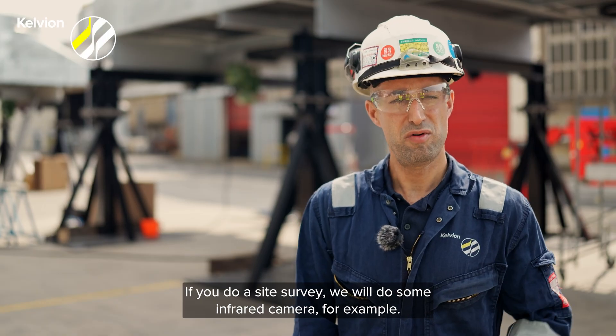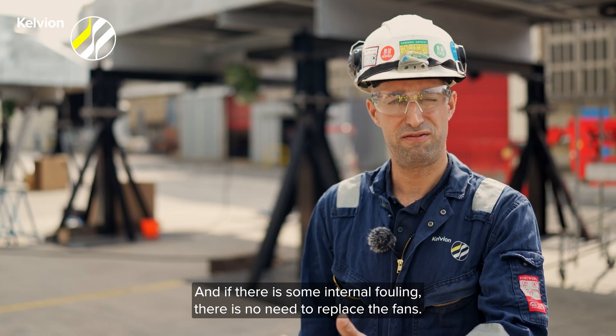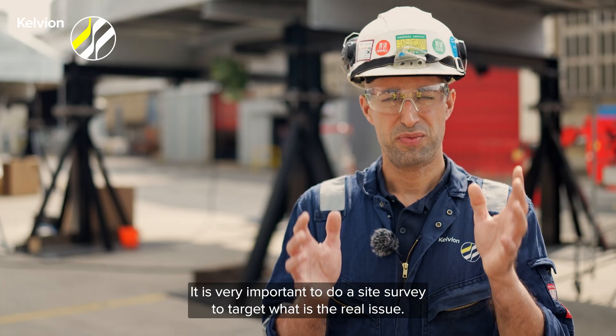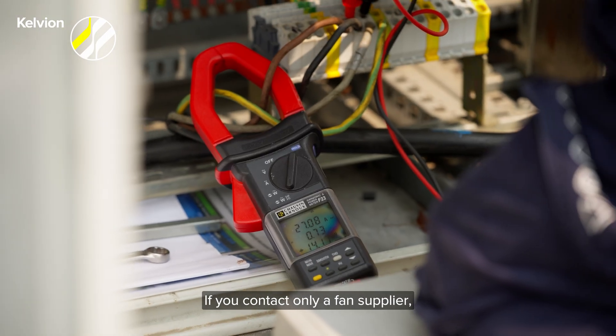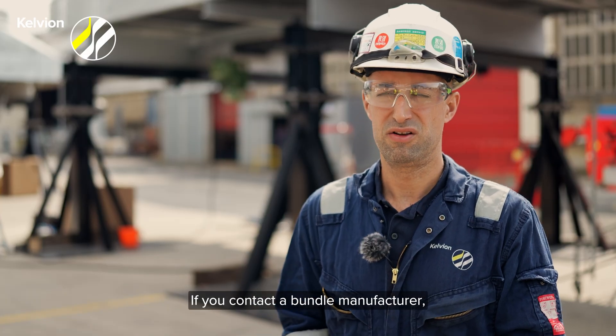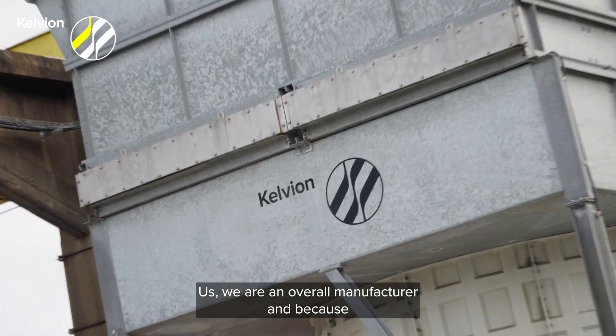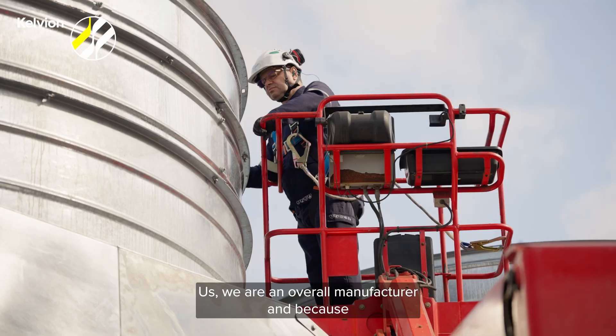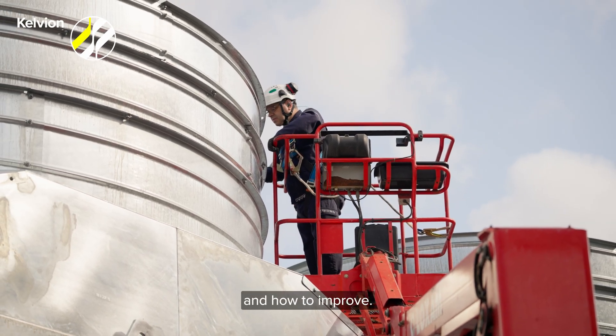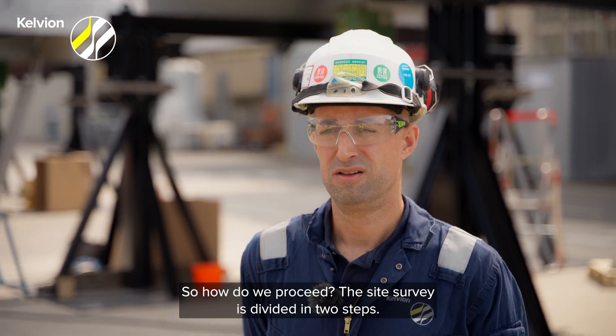If you do a site survey, we will use an infrared camera, for example, and we will find out if there is some internal fouling. And if there is some internal fouling, there is no need to replace the fans. It's very important to do a site survey to target what is the real issue. If you contact only a fan supplier, it will tell you that the fan has to be replaced. If you contact a bundle manufacturer, it will tell you that you need to replace the bundles. We are an overall manufacturer, and because of the site survey, we will know what is the issue and how to improve — so you will not do something useless for you and for the air cooler.